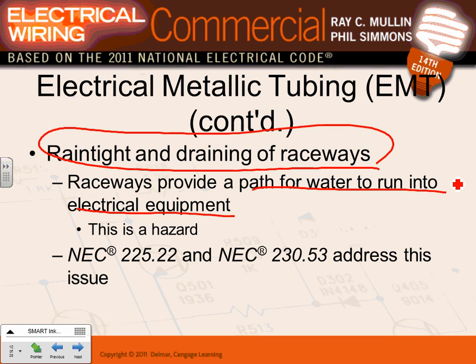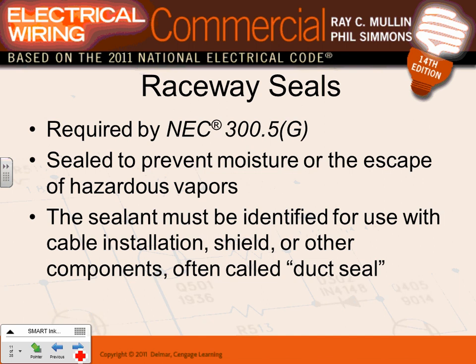You put a conduit and water condensation comes through it. If it's watertight, no problem. But condensation creates water that channels right to the top of your equipment. You and I understand that water and electricity don't mix. You're going to have an arc flash inside your system. So you must provide a means of channeling that water away from the conduit and equipment.